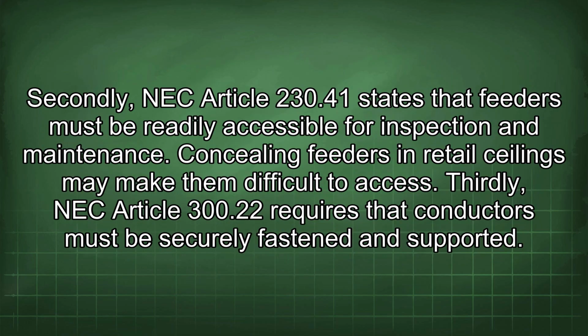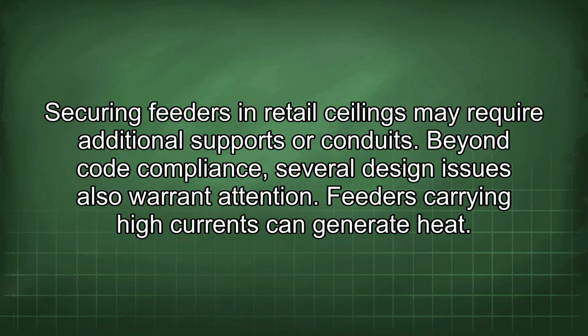Secondly, NEC Article 230.41 states that feeders must be readily accessible for inspection and maintenance. Concealing feeders in retail ceilings may make them difficult to access. Thirdly, NEC Article 300.22 requires that conductors must be securely fastened and supported. Securing feeders in retail ceilings may require additional supports or conduits.